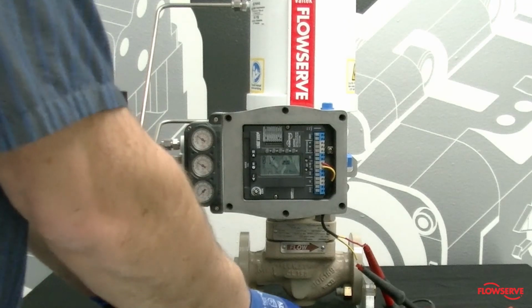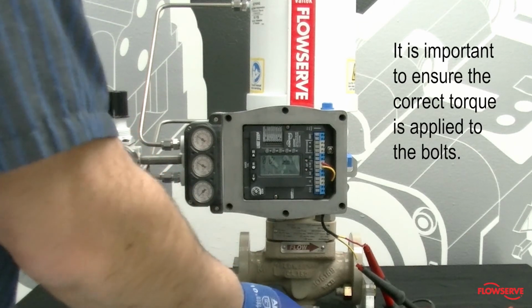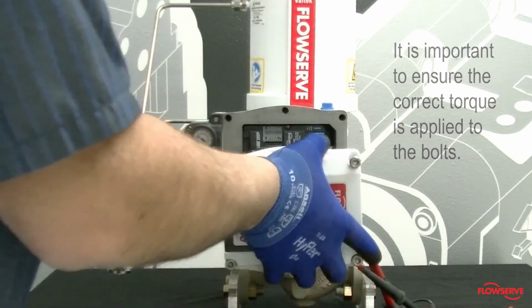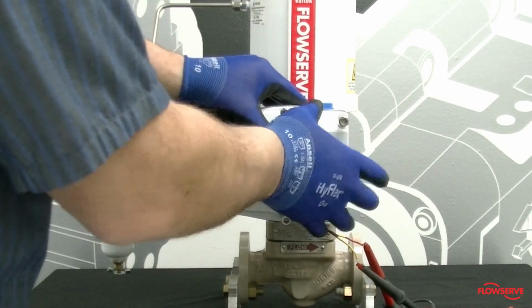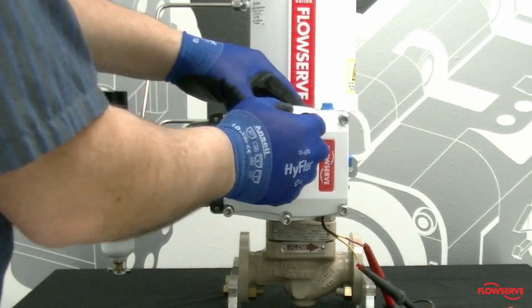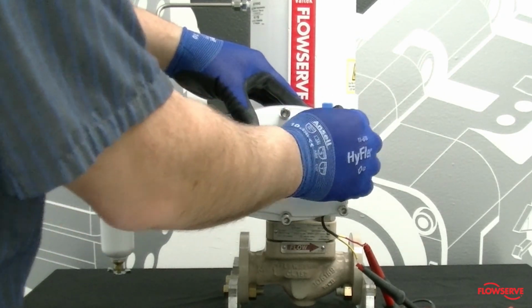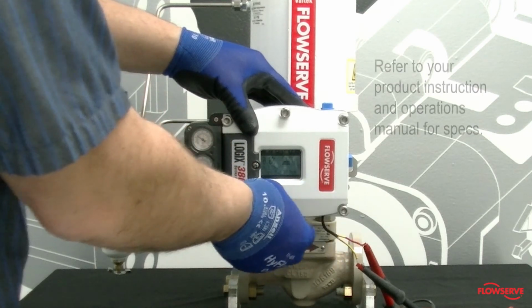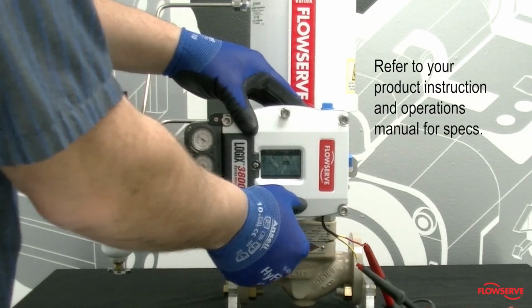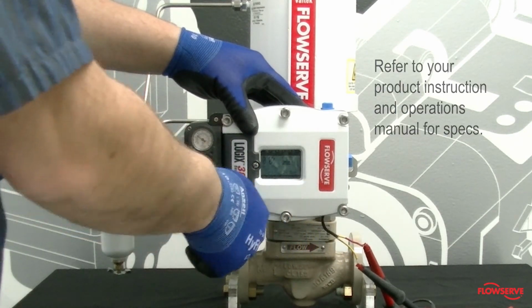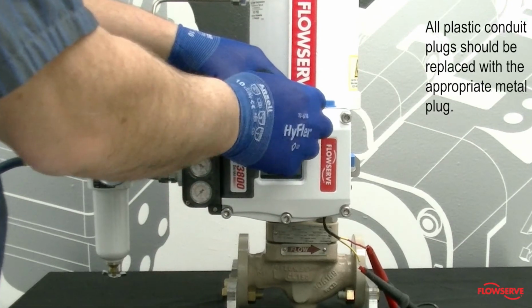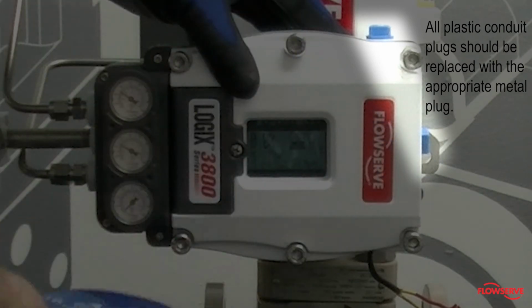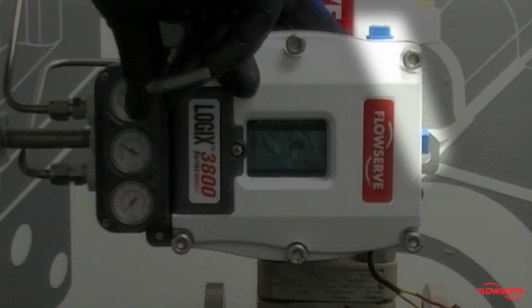When reinstalling the main cover, it is important to ensure the correct torque is applied to the bolts. This will help to maintain the required gap between the cover and the housing and meet regulatory certification. Please refer to your product instruction and operations manual for specifications. Lastly, all the plastic conduit plugs should be permanently replaced with the appropriate metal plug. This will help to ensure no contamination is introduced into the positioner.